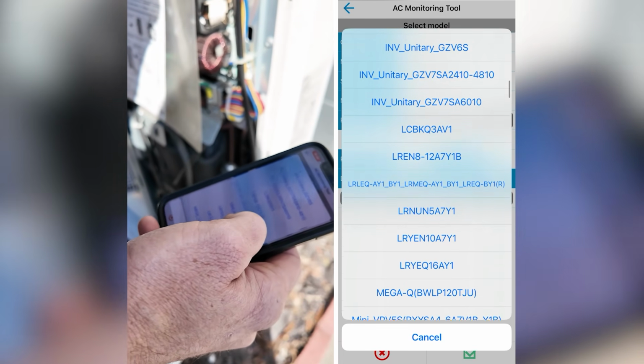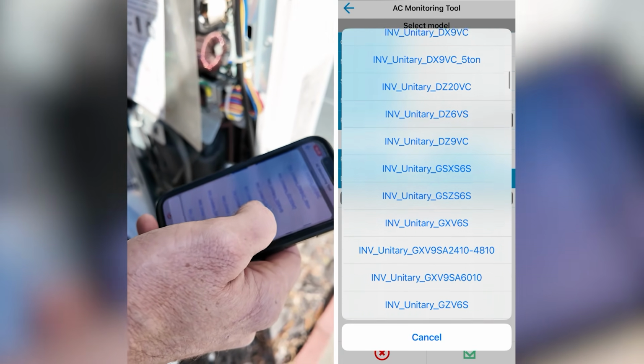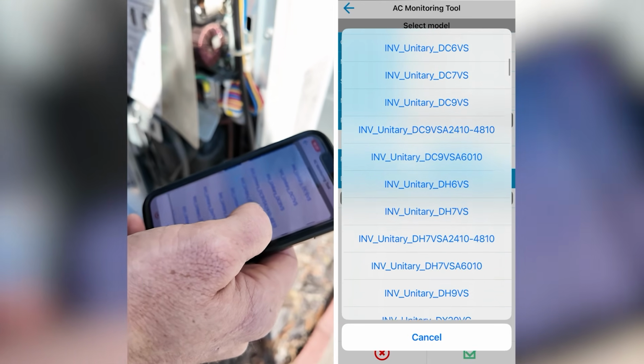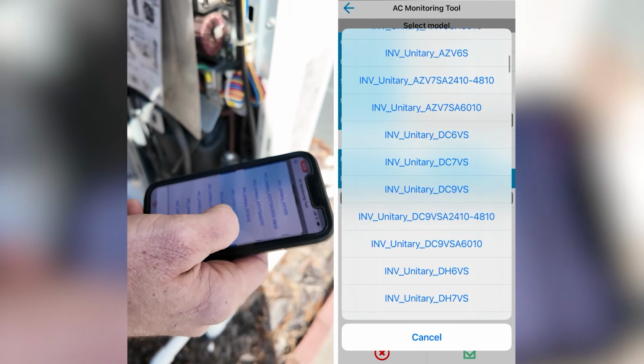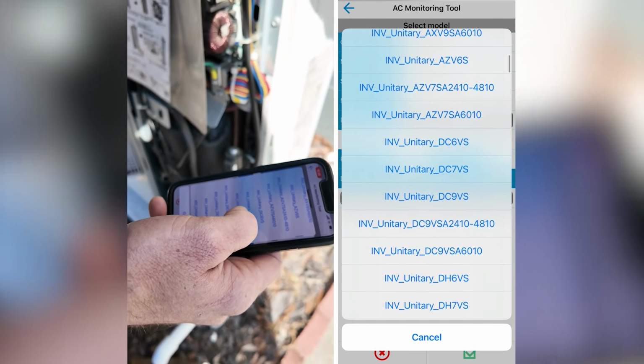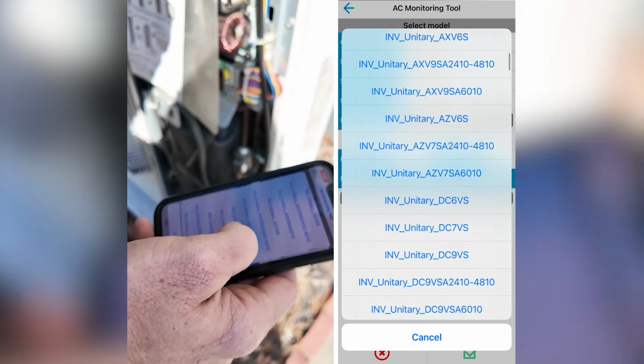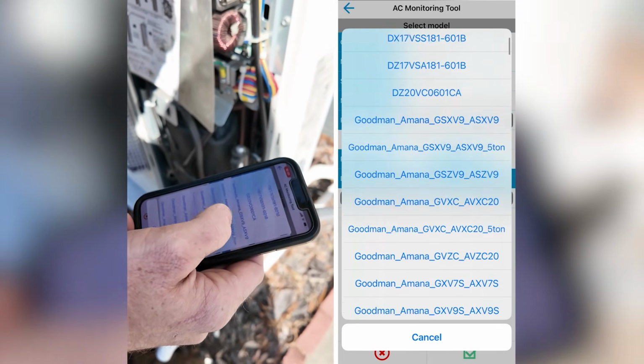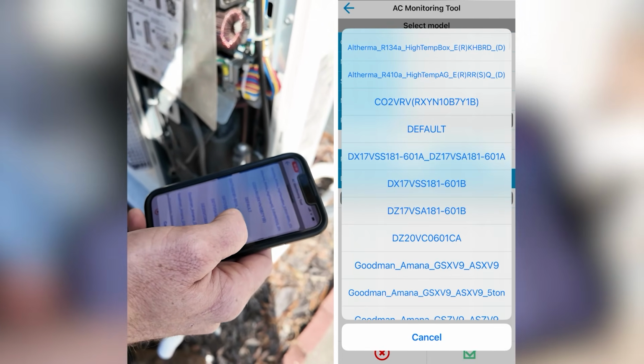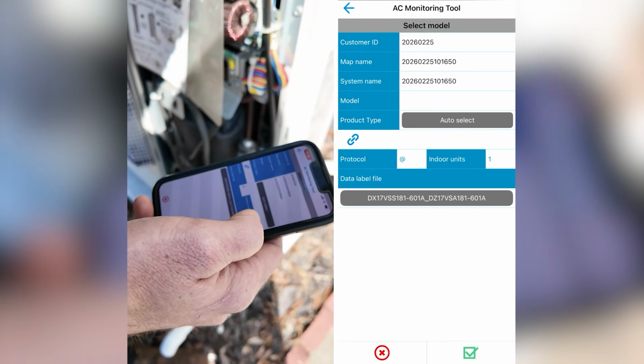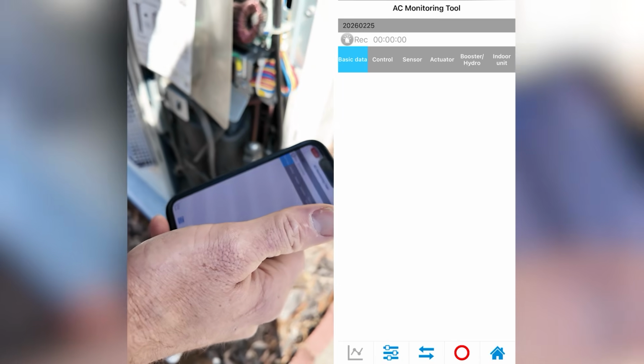You just want to make sure that in this list, if you can't find the exact model number you're looking for, you find the older piece of equipment. And so for that, the D stands for Daikin, Z, right, is the inverter-driven equipment. So we're going to go down here and we're going to go back up and click on the DZ17. Okay, hit the green check mark. And now it's going to start pulling in all the information.